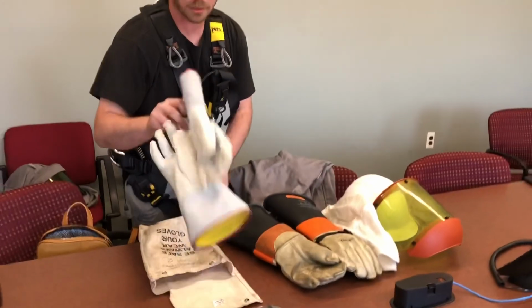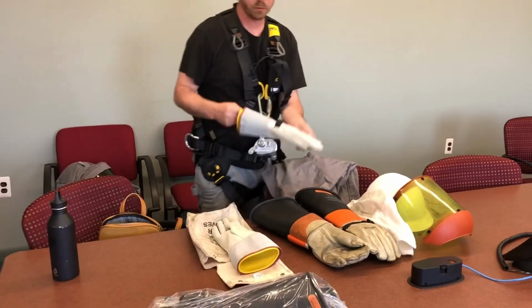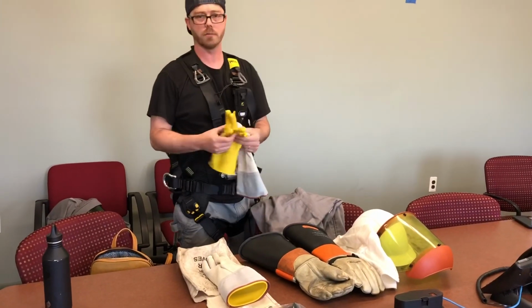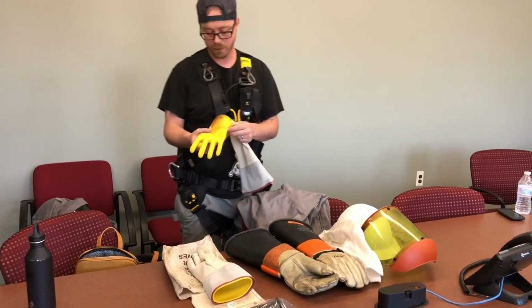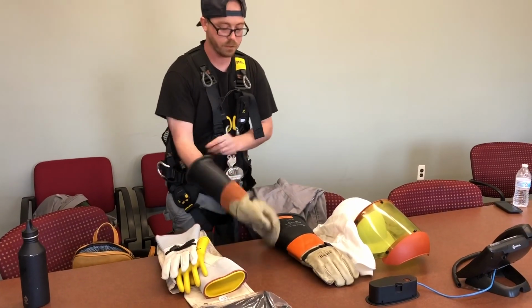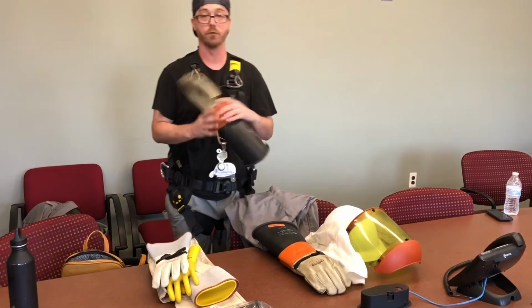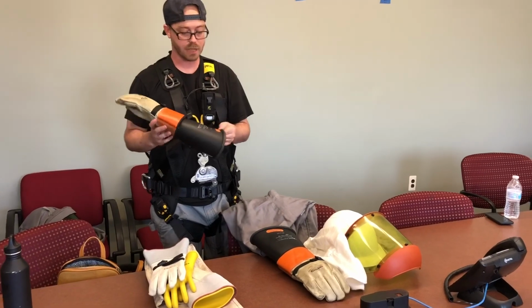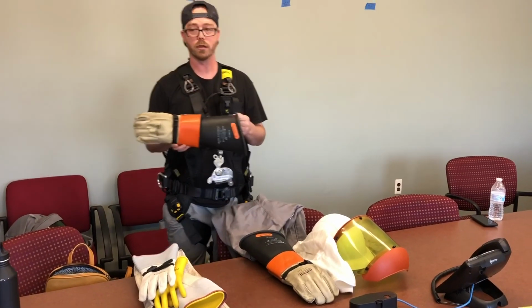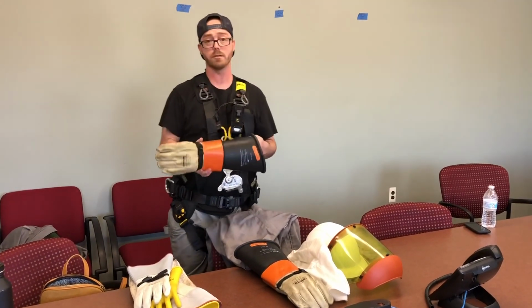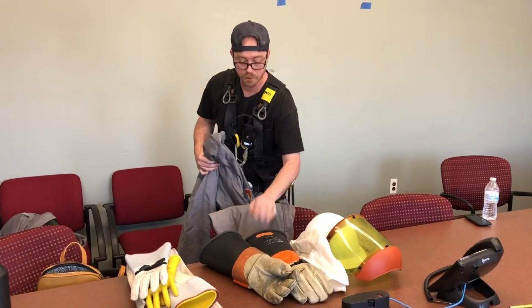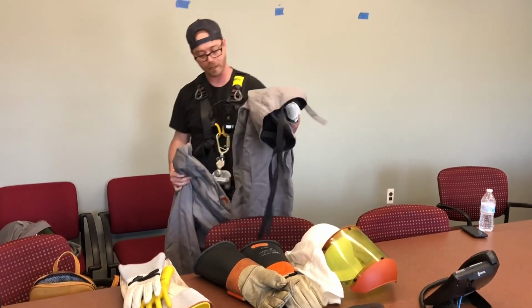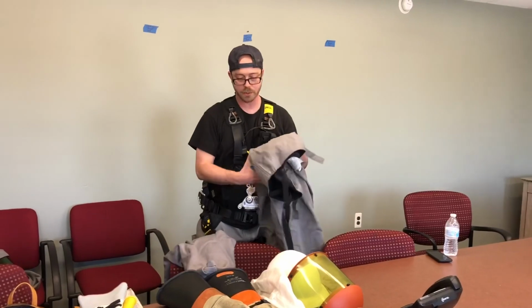These gloves here are just your typical class 0 gloves. These are the rubber insulated gloves you'd use when working on some of the lower voltage equipment. And these bigger ones are for high voltage work, so these are class 4, rated up to 36,000 volts. If you're going to use these, you've got this 40 calorie suit, which is essentially a suit to help in case of an arc flash or blast.